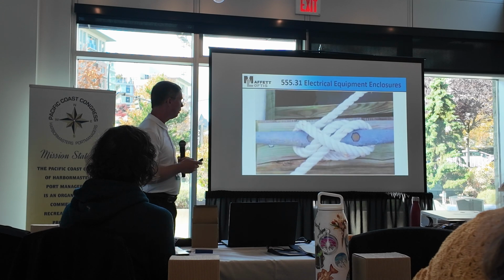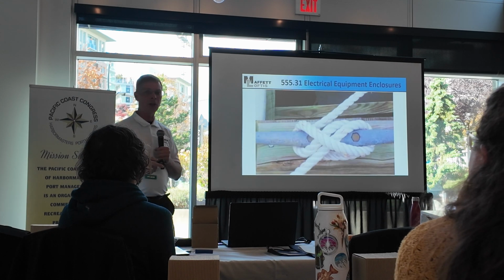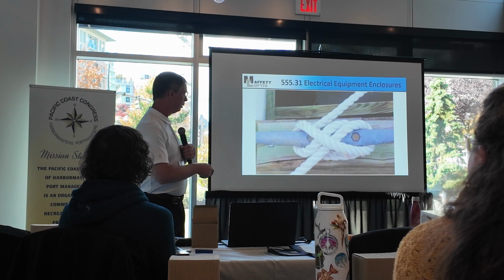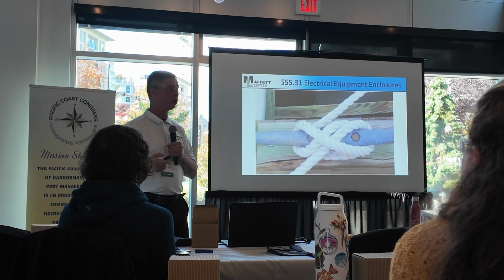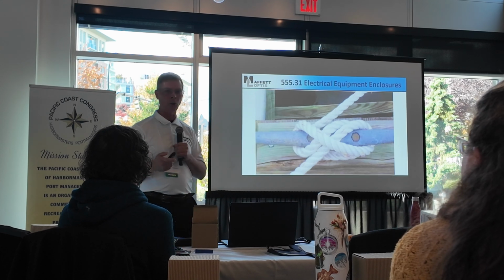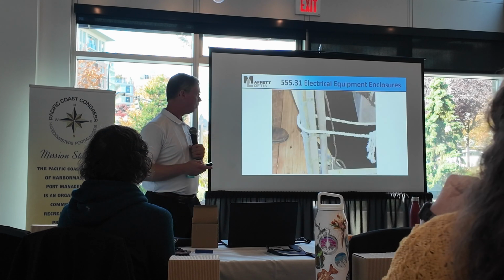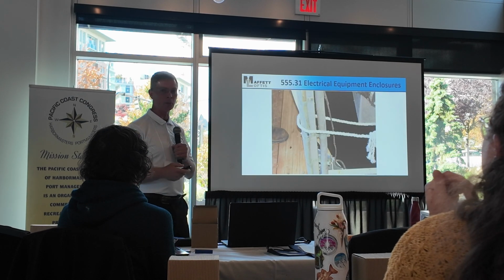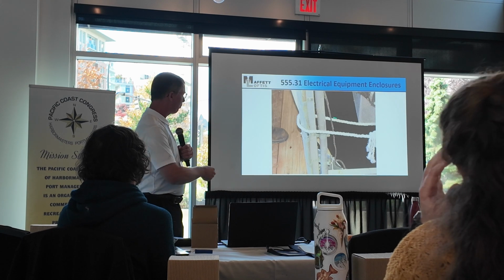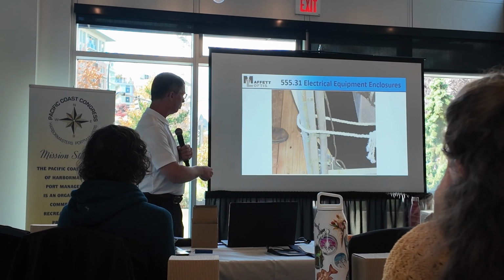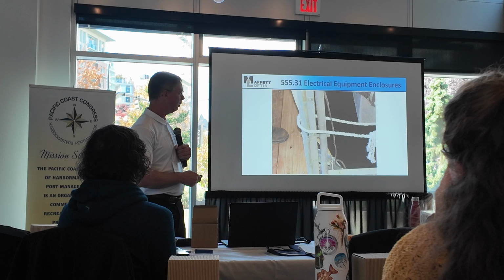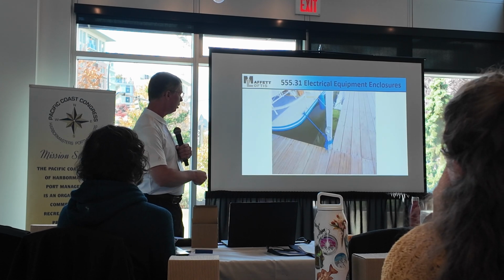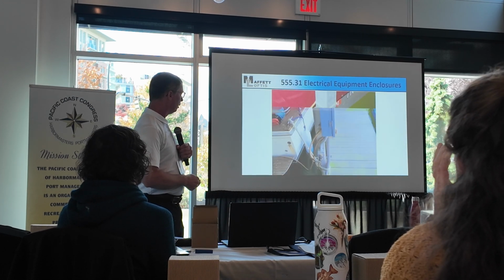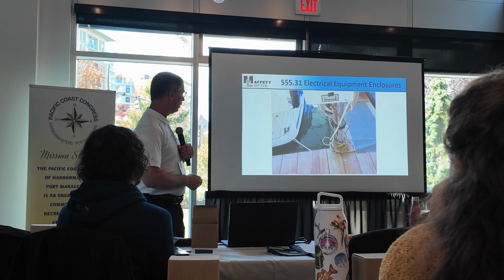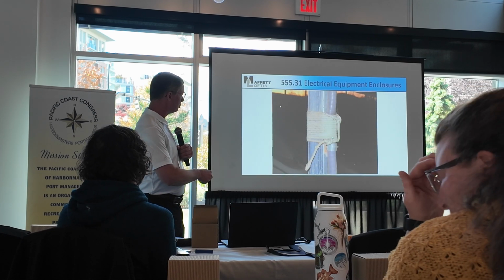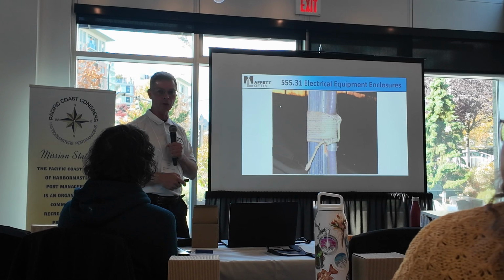Now, as we go on, this right here is something that you should be managing. Think about your mooring cables. They cannot interfere. There's a code, 310, that says mooring cables can't interfere with the electrical system. But if you look at this, these are covered docks, boathouses, whatever it may be, and they wrap their mooring cables around the electrical. And you see it's already broken the conduit down there. And I see this constantly, everywhere. And think about how tight that is. Do you think it's damaging the electrical conductors inside that?